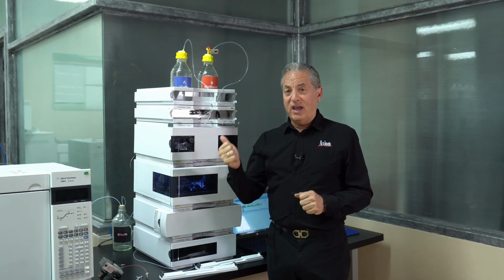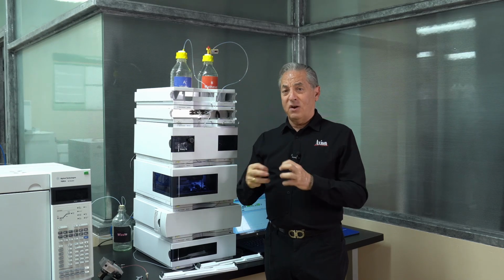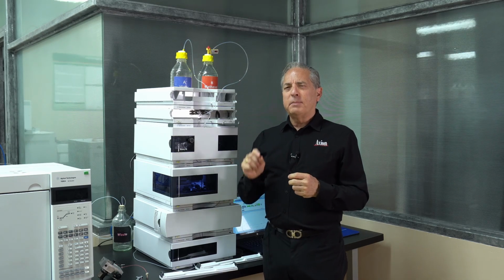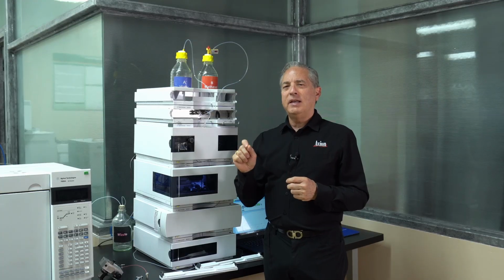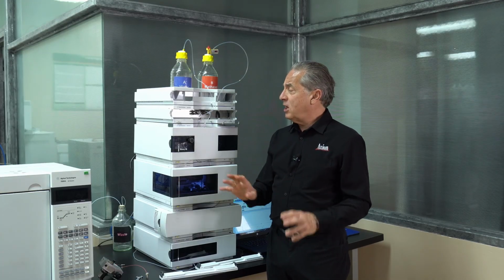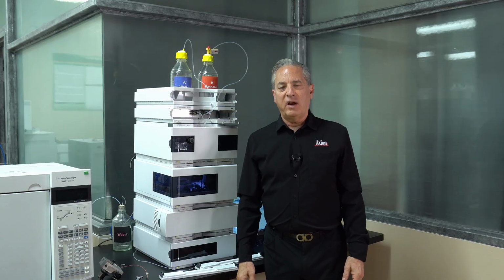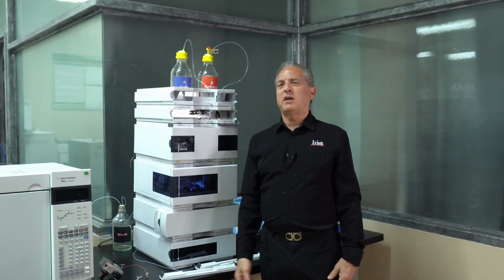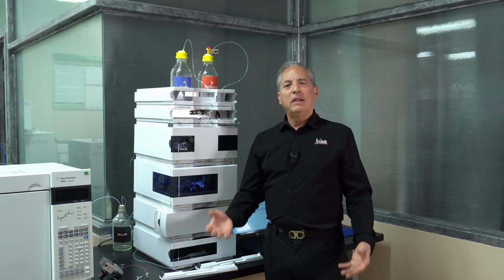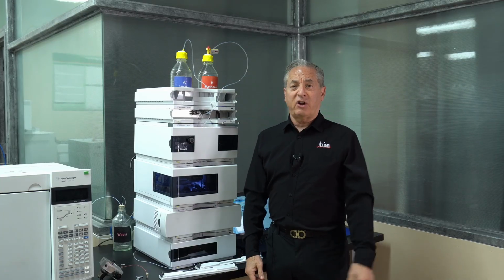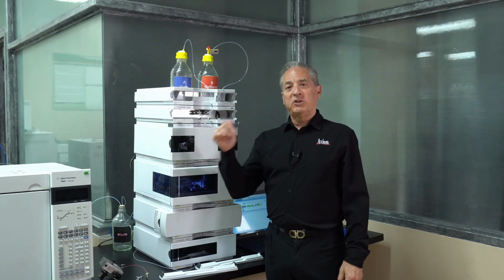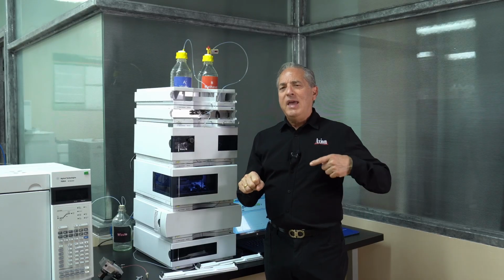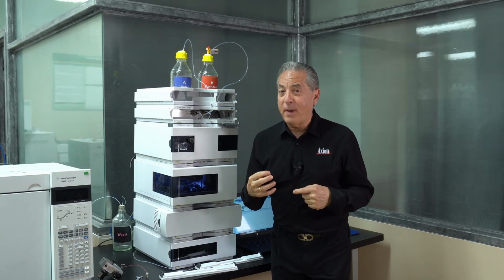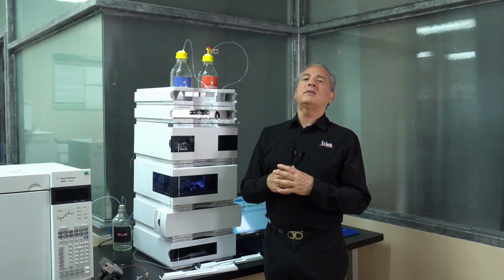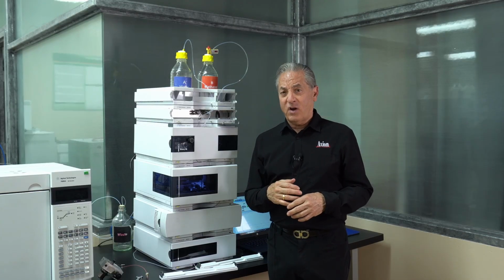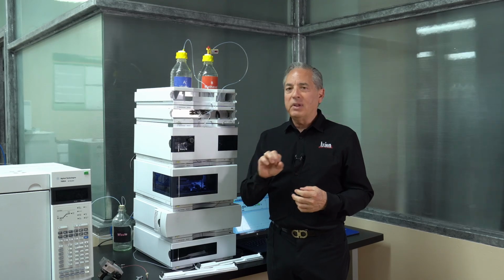Okay, I've got 4 channels, A, B, C, and D. Each one is independent. They're their own bundle of tubing. The problem is the tubes are really, really tiny. So let me tell you the worst case scenario. Someone has a phosphate buffer running in channel A, at a high concentration of phosphate, 25 millimolar, 50 millimolar. Life is good. Then they decide they're going to put acetonitrile in channel A. I don't know why, acetonitrile should go in channel B, but if you were to put acetonitrile in a channel that already had a phosphate buffer in it, phosphate buffers are notoriously insoluble in acetonitrile. They will crash out and precipitate, completely blocking that tube.